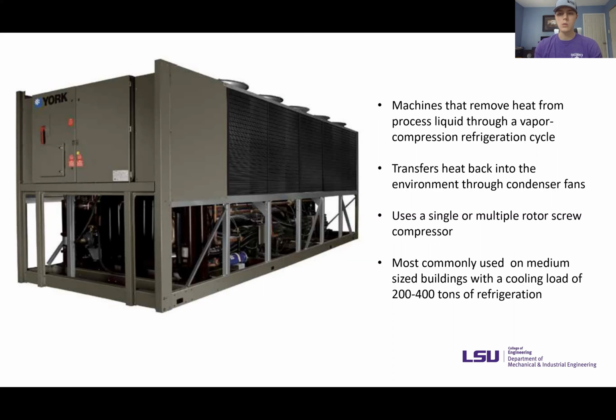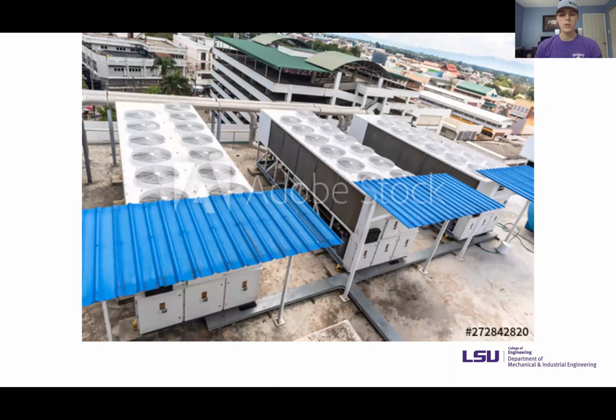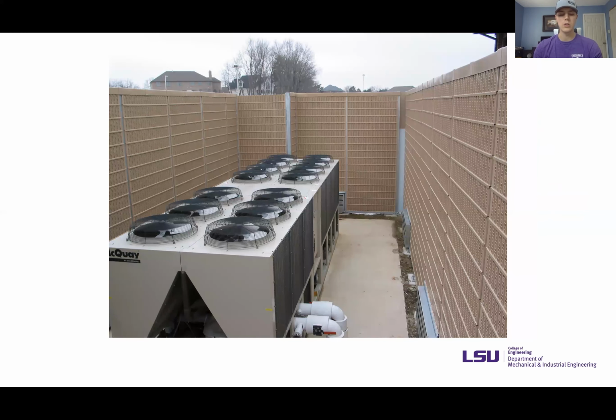They use a single or multiple rotor screw compressor. These types of compressors are generally used to accomplish a chiller range from about 70 to 500 tons. And these units are most commonly used on medium-sized buildings with a cooling load of 200 to 400 tons of refrigeration. They're typically installed on the top of a building to provide adequate airflow to the condenser fans, or because there's limited space. They can also be installed on the ground floor levels, such as this one.